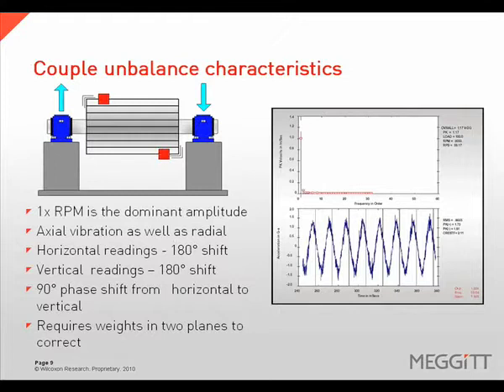Couple unbalance will exhibit a vibration response similar to force unbalance, but will also exhibit high axial amplitudes as well as high radial amplitudes. The horizontal and vertical phase readings should exhibit a 180 degree phase shift, with a 90 degree phase shift from the horizontal plane to the vertical plane. Couple unbalance will require two-plane or multi-plane balancing weight placement to correct.